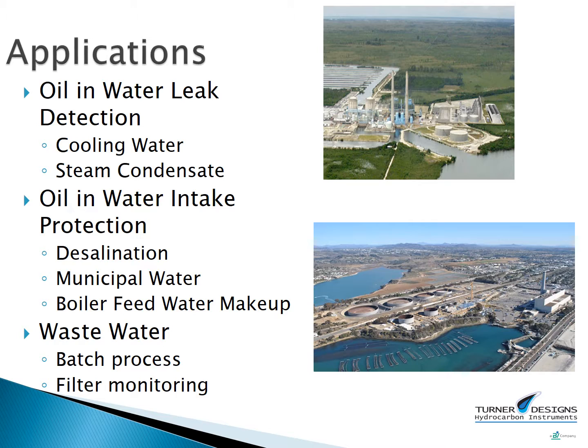The TD120 is designed for detection of oil at low concentrations in mostly clean water service. For instance, lubricating oils, hydraulic oils, transformer, and turbine oils all can be detected in cooling water services. Likewise, heavy fuels, crude oil, and such can be measured in steam condensates at a refinery or power plant.